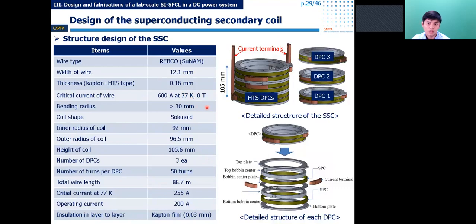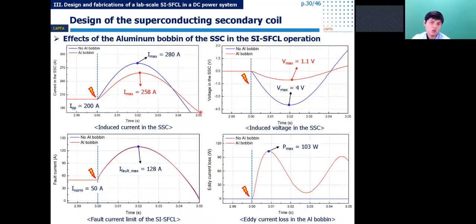And this slide shows the detailed design specification and structure of the secondary coil. A circular shape double pancake coil was applied. There are 3 DPCs with 50 turns each DPC. It will be wound on the aluminum bobbin. So the question is why we use the aluminum bobbin in the secondary coil. The reason is that the aluminum bobbin, like a single turn coil, separates the secondary coil from the magnetic change in the iron core during the transient fault. Thereby, it can reduce the induced current and the induced voltage in the secondary coil.